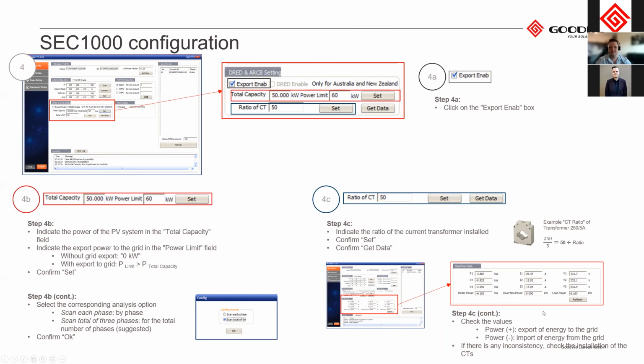Thereafter, we can then switch the inverter's AC on. And if everything is correct, then it'll probably take roughly 5 to 15 minutes for the controller, then we should start seeing our inverters start to output power. We can then also keep observing here and see the inverter's power that's producing. And then we can look at the meter power versus the inverter power, and that will give our load power. So if the inverter is running, we can also calculate the current with the voltage. This we can see that our numbers coincide. If this is then vastly out, it could be that the site's power factor is just not very good, and the inverter's 1.0 output power factor is negatively impacting the current power factor. So that's just something you have to take into account. Site power factor is not necessarily the inverter's responsibility, but you can also adjust the inverter's power factor to try and compensate for this.